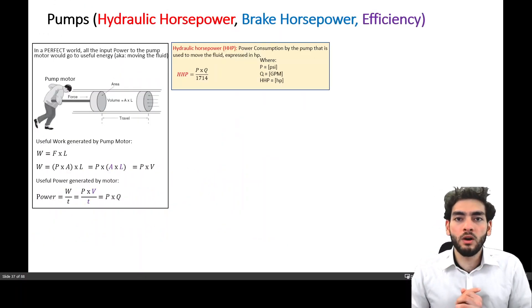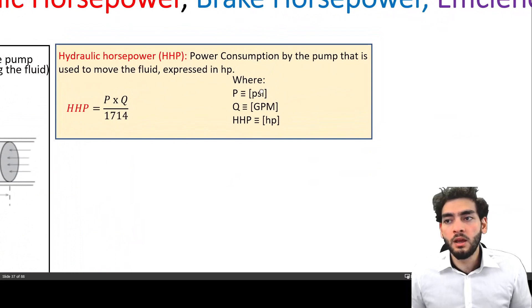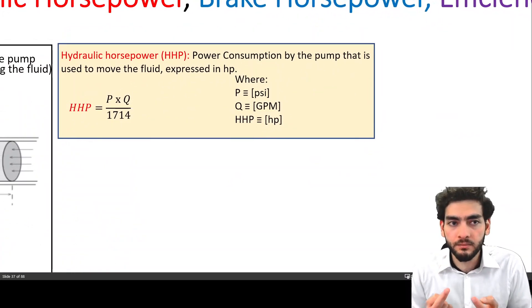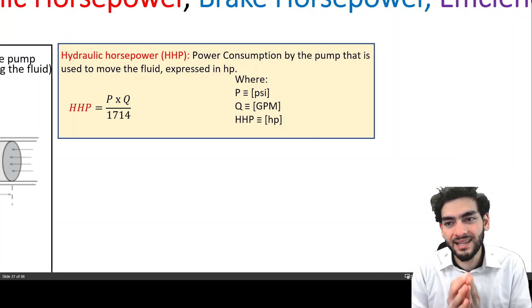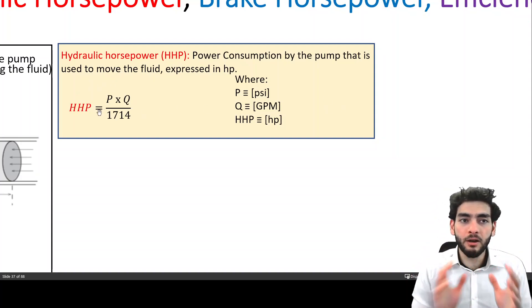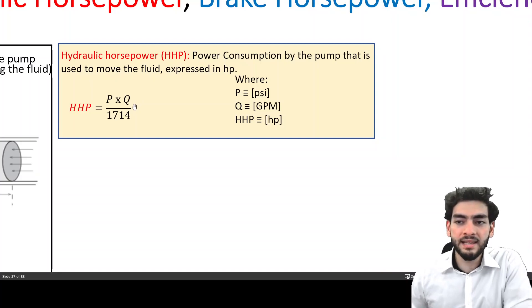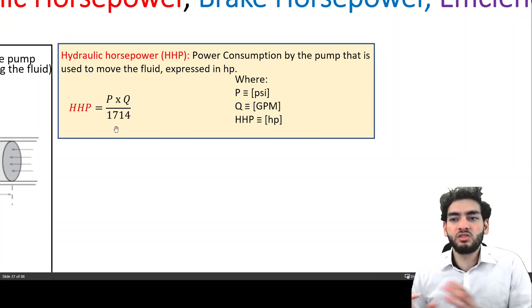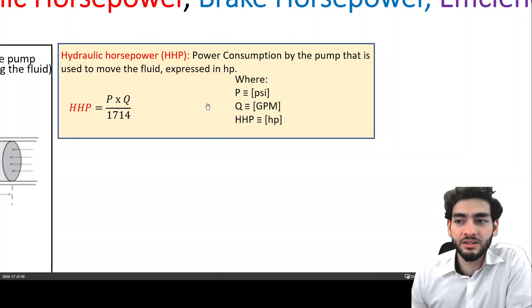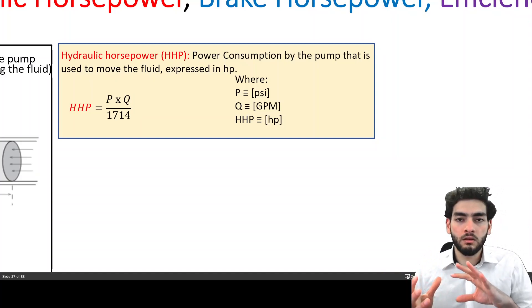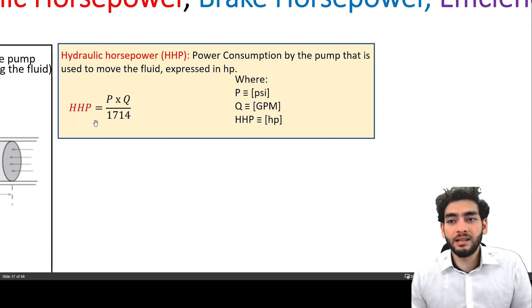The first parameter to be aware of is hydraulic horsepower. Hydraulic horsepower is the power consumption by the pump that is used to move the fluid — it is the useful energy being transmitted to the fluid itself. The hydraulic horsepower is pressure times the volumetric flow rate. The number we divide by — 1714 — is a unit conversion, because pressure is expressed in PSI and volumetric flow rate in gallons per minute, and dividing by 1714 converts that power to horsepower units.